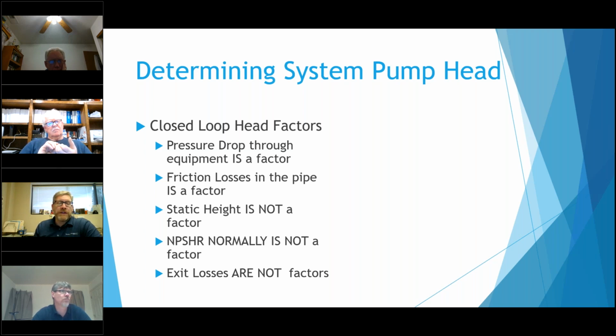Conversely, the NPSHR, the acronym is net positive suction head required, is normally not a factor because every pump needs a certain amount of pressure to operate correctly so you don't cavitate the pump. You're not causing issues with the pump. In fact, if you don't have enough, the pump sounds terrible. It sounds like you're pumping rocks through it, when actually what's happening is there are little bubbles inside of the impeller, and they're kind of imploding onto the impeller.